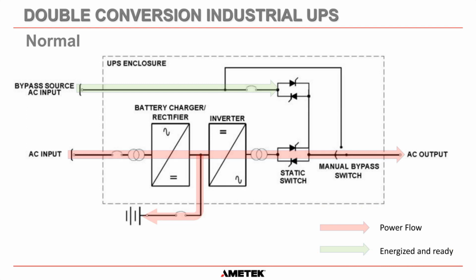Okay, so in normal operation, you can see that power comes from the AC input here, comes into our battery charger rectifier, and then the battery charger rectifier will regulate the output voltage, the DC voltage, at what is required to charge the batteries. In truth, the inverter doesn't care what that voltage is. Now, yes, it does have to be within certain specifications, and for us, it is usually 105 to 140 volts DC for a 60 cell system.